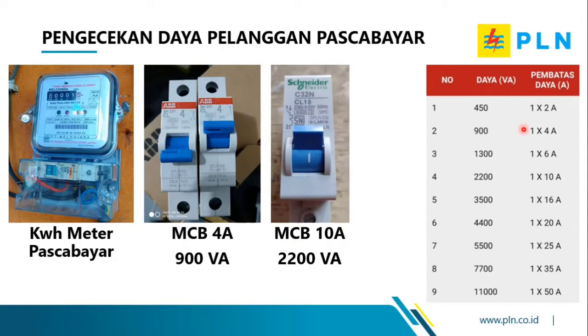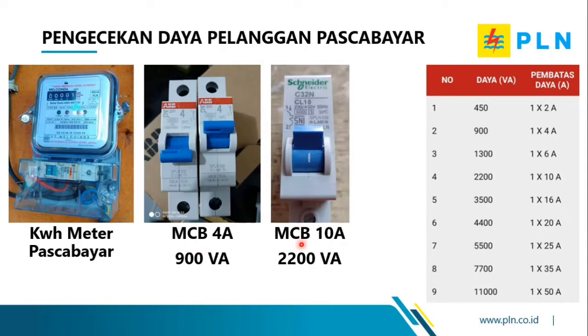Jika menggunakan MCB 4 ampere maka dayanya adalah 900 VA. Kemudian jika di lapangan kita jumpai MCB dengan tulisan CL10 — CL10 ini adalah pembatas arus 10 ampere. Jika menggunakan MCB 10 ampere maka daya pelanggan tersebut adalah 2200 VA. Jadi untuk pelanggan pasca bayar, kita bisa mengetahui daya kontrak PLN dari pembatas MCB yang digunakan pada KWH meter tersebut.